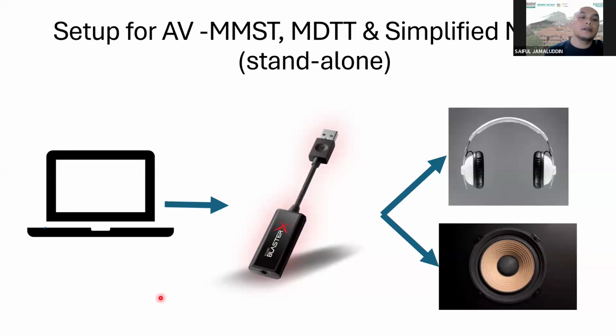But as I mentioned earlier, the test is more flexible because you're testing in noise and not in quiet, so you don't have to be too concerned about absolute sound pressure levels. And when the noise and the signal come out from the same transducer, what we're more concerned about is the calibration of the SNR. So as long as the SNR can be maintained, then the results will still be reliable. So you do not need to have an audiometer for the speech test. If you want to have a standalone system, you just need a PC. You need an external sound card to ensure that the sound quality and the intensity of the sound can be made loud enough. And then, of course, you have to plug your external sound card into any reliable transducer, headphones, and also any reference speaker that you can find. Right.